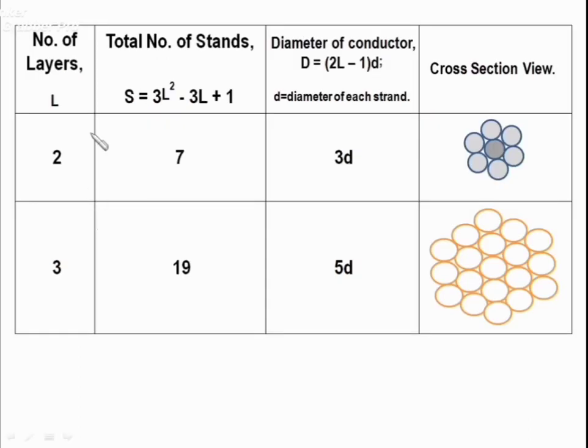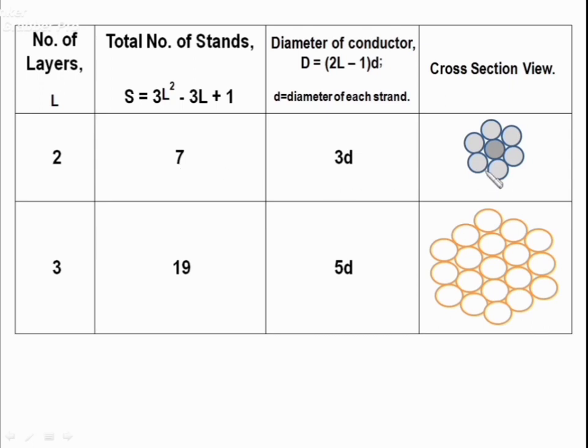In this table, L denotes number of layers. Total number of strands is denoted by S = 3L² − 3L + 1. Diameter is represented by D = (2L−1)×d, where d is the diameter of each strand. If number of layers is 2, you can have 7 total strands. If number of layers is 3, you can have 19 total strands — you can observe the cross-sectional view.